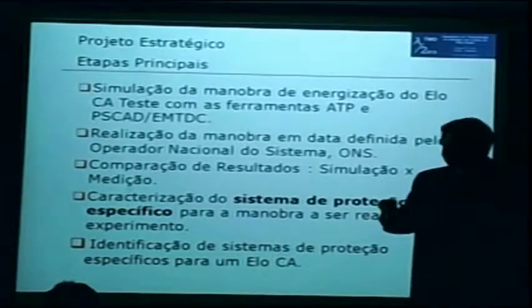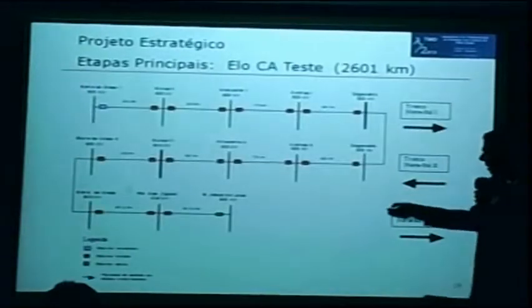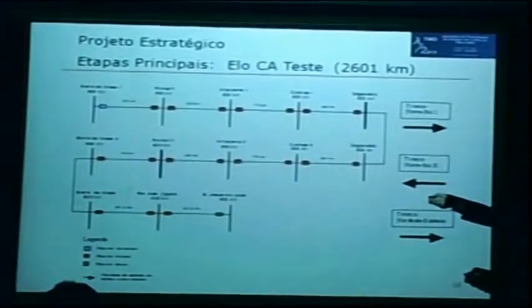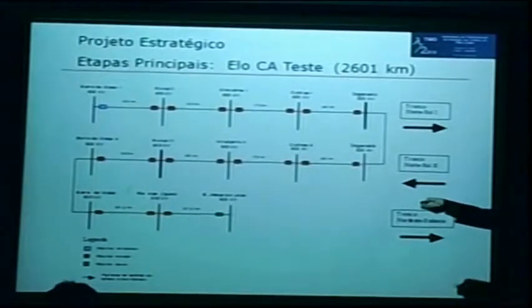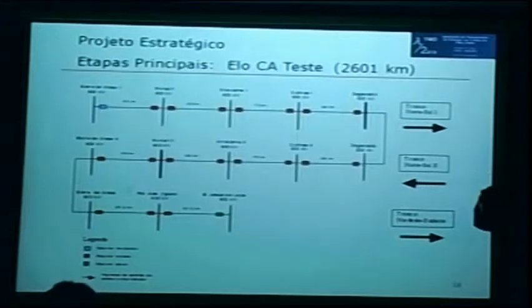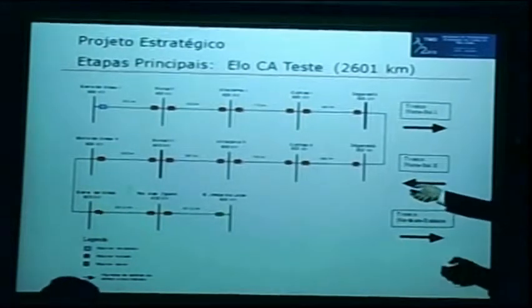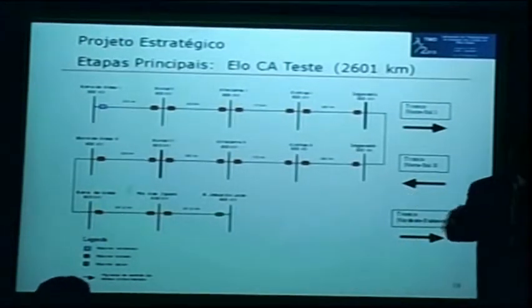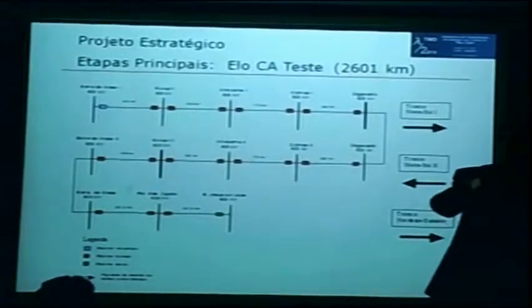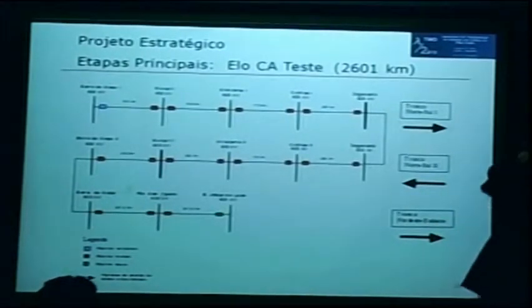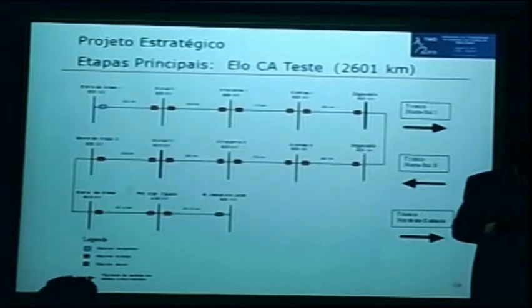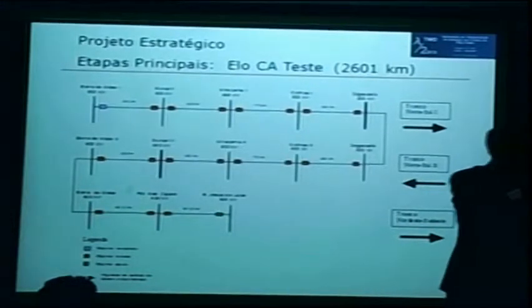We're also characterizing the specific protection system for the CA link. A question that arises is about Serra da Mesa, where the system belongs to Furnas, and there is a distance relay providing protection for this line. The question is, can this relay provide protection for the whole of the 2,600 kilometers of line?